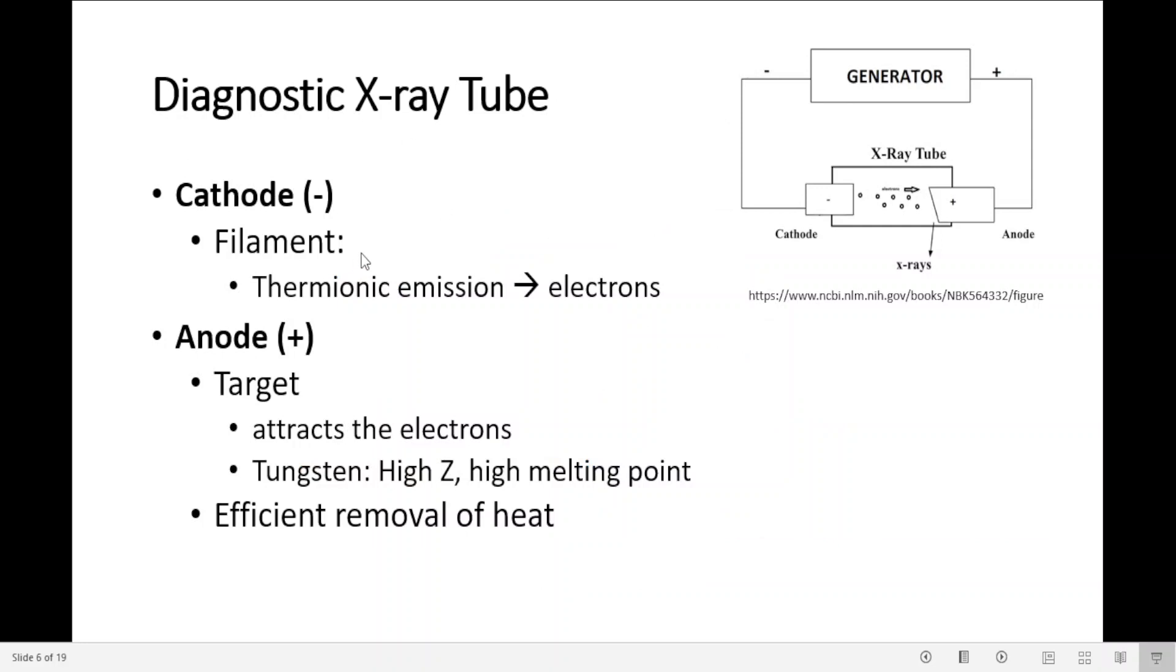So we have a cathode, which is negative. It has the filament where electrons are emitted through thermionic emission. The anode is positive, has the target, attracts the electrons. It's made of tungsten, usually because it has a high atomic number, high melting point. Efficient removal of heat from the targets is an important requirement for the anode design.